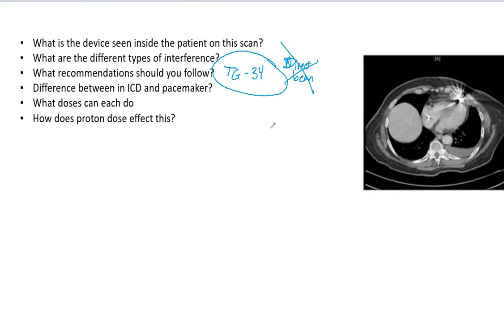You want to estimate the doses. You want it to be less than two gray, the pacemaker dose to it less than two gray. If it is greater, you can test before and after the treatment.